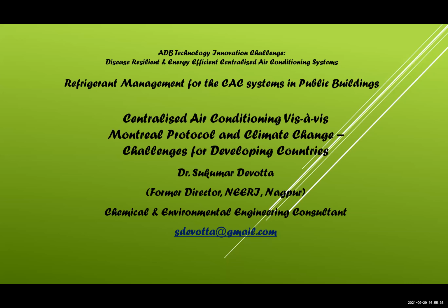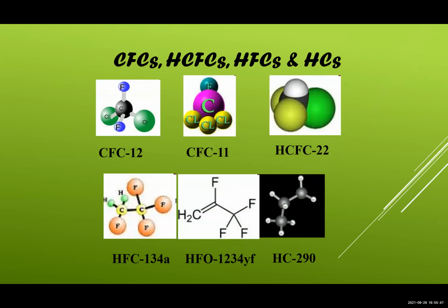And I'm going to speak mostly on refrigerant choices with respect to how do you deal with Montreal Protocol and climate change, and what are the issues for developing countries. So just in case people don't understand the refrigerants, because it's too easy to say HCFC, HFC, but then you have to understand that each has its nomenclature. So when we have a chlorine and fluorine and carbon, then we call it CFC.